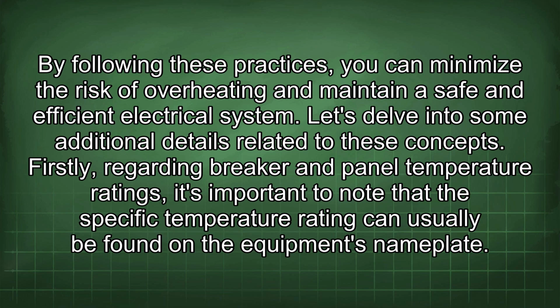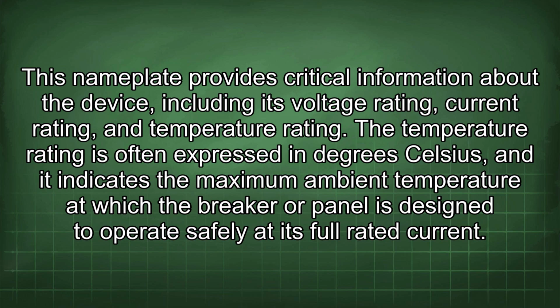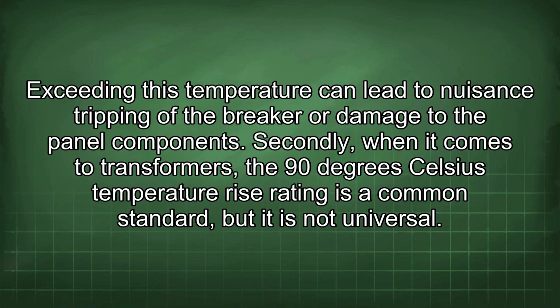Firstly, regarding breaker and panel temperature ratings, it's important to note that the specific temperature rating can usually be found in the equipment's nameplate. This nameplate provides critical information about the device, including its voltage rating, current rating, and temperature rating. The temperature rating is often expressed in degrees Celsius, and it indicates the maximum ambient temperature at which the breaker or panel is designed to operate safely at its full rated current. Exceeding this temperature can lead to nuisance tripping of the breaker or damage to the panel components.